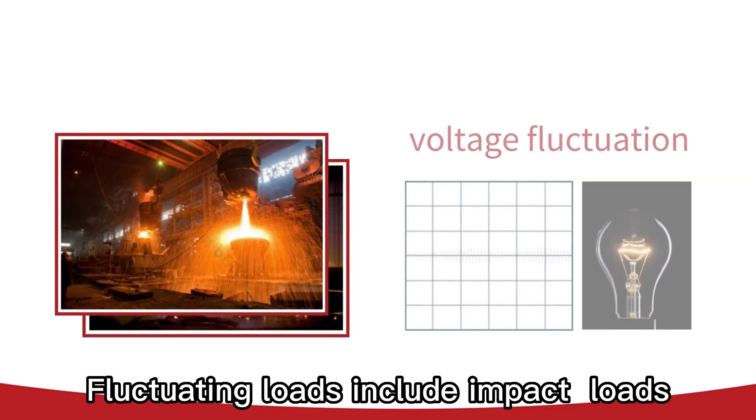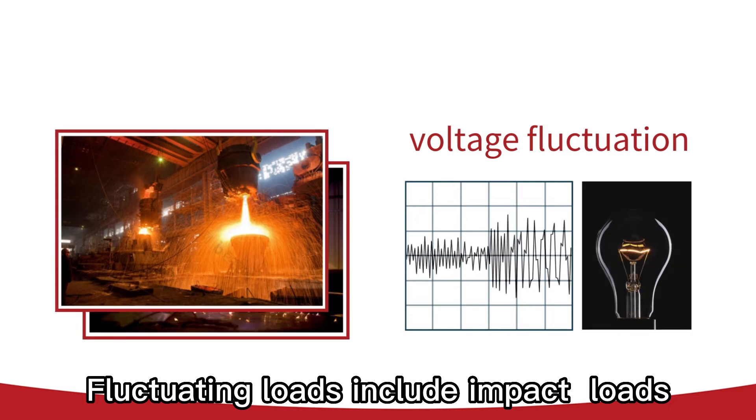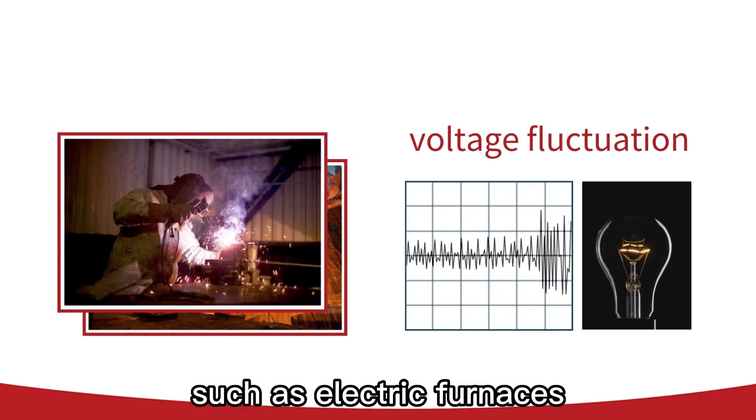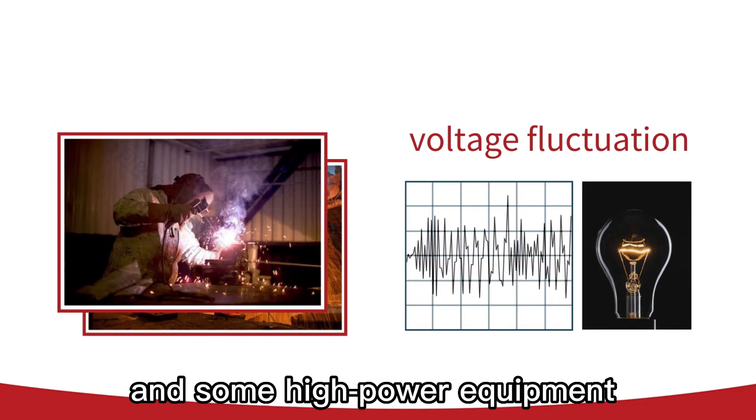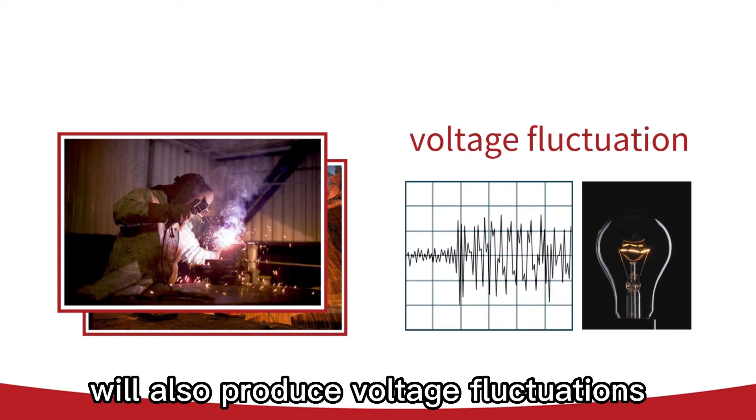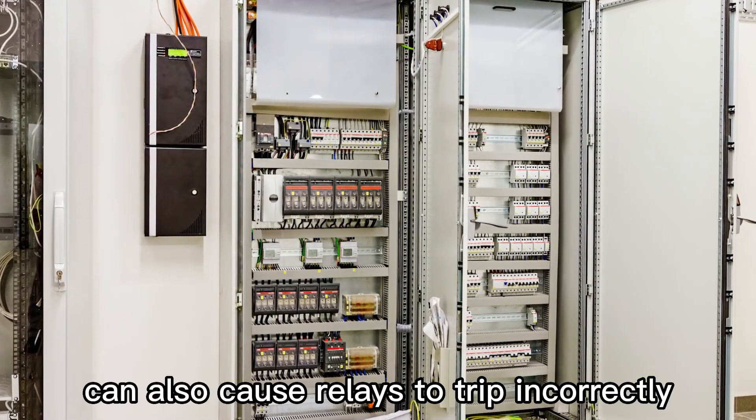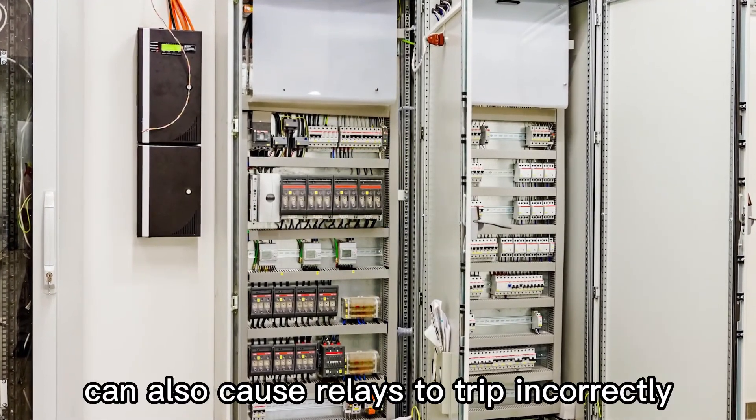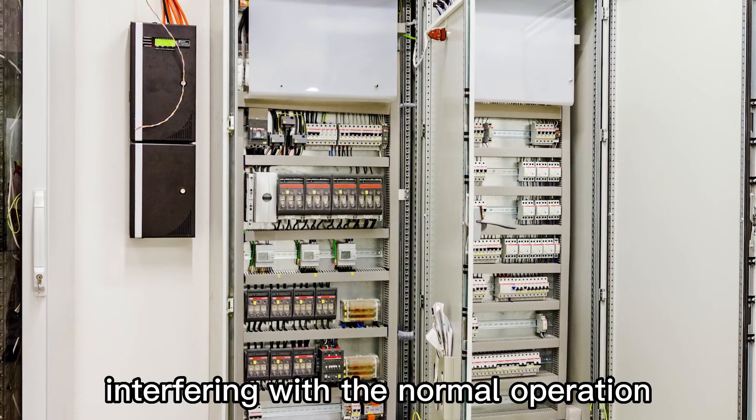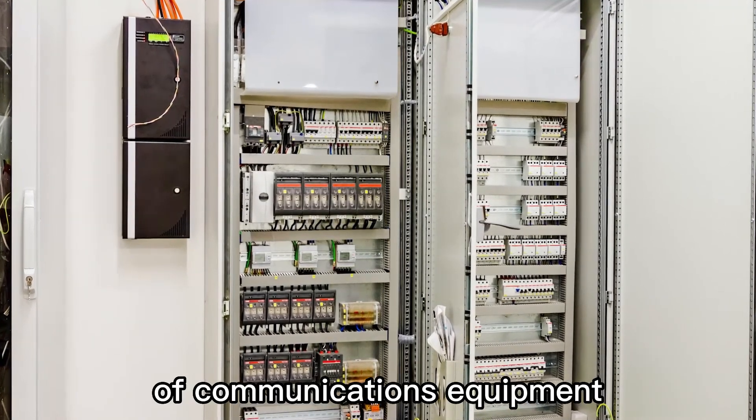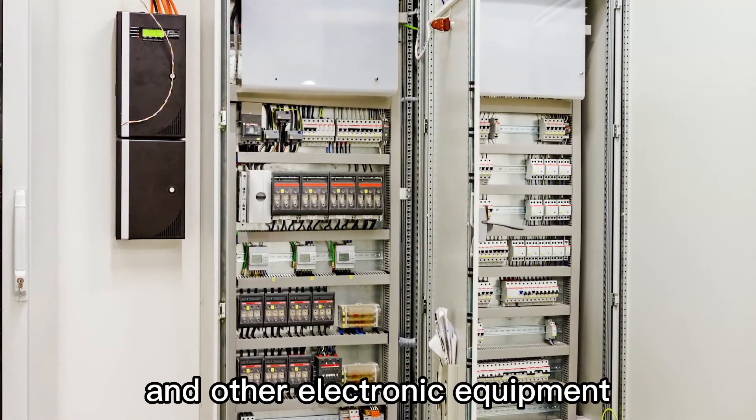Fluctuating loads include impact loads such as electric furnaces and electric welding machines. And some high-power equipment will also produce voltage fluctuations when switching. Voltage fluctuations can also cause relays to trip incorrectly, interfering with the normal operation of communications equipment and other electronic equipment.